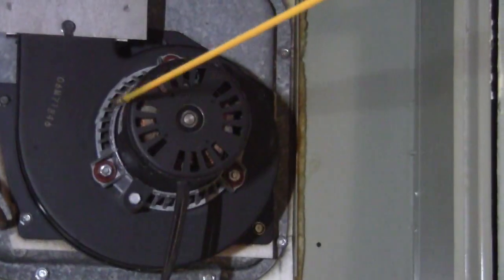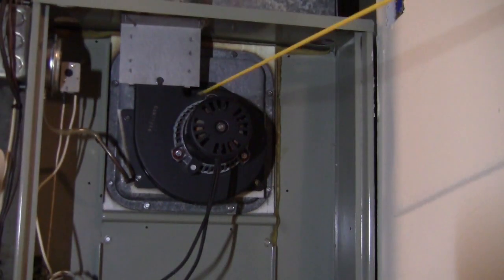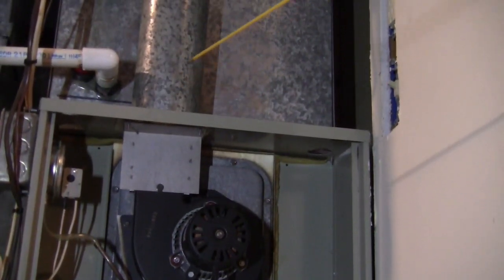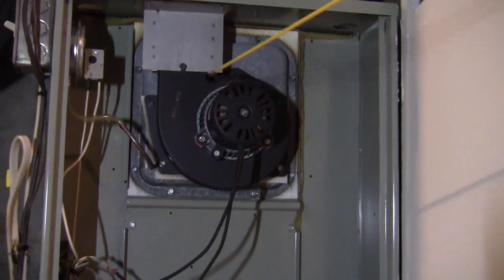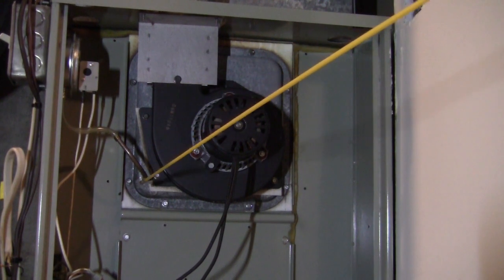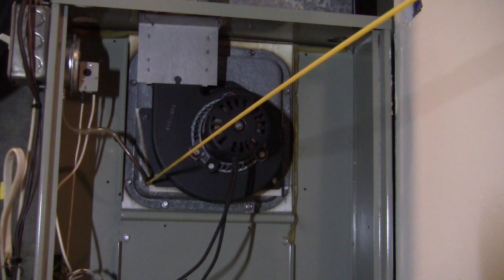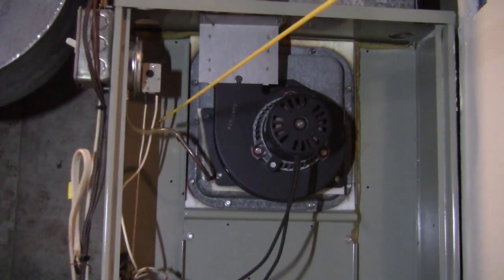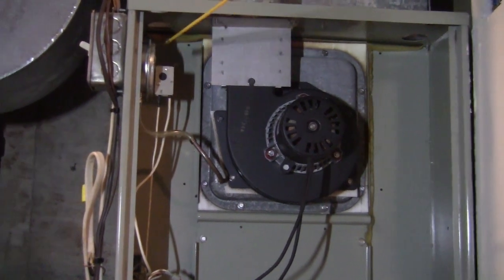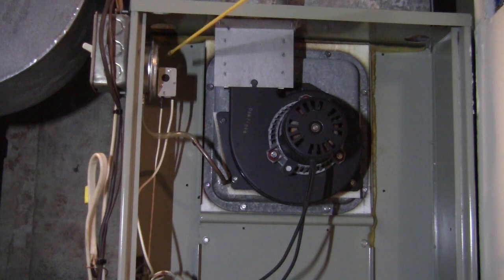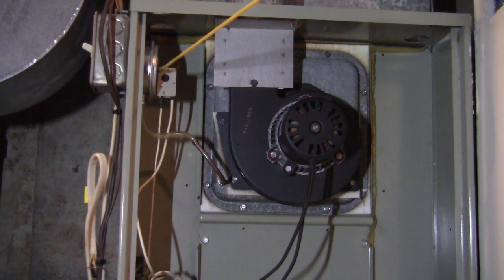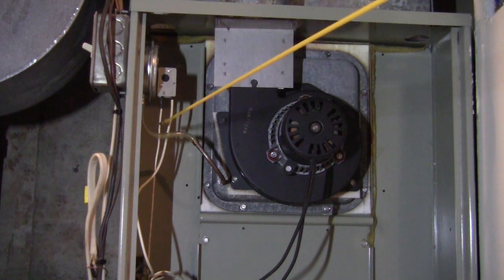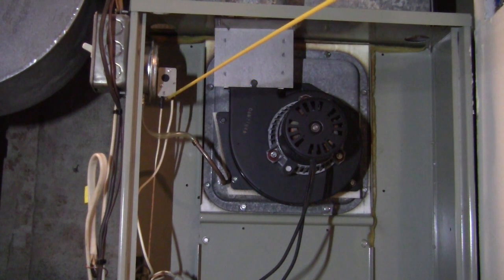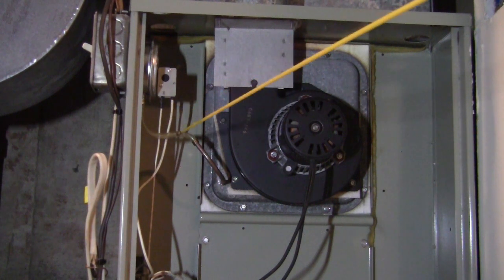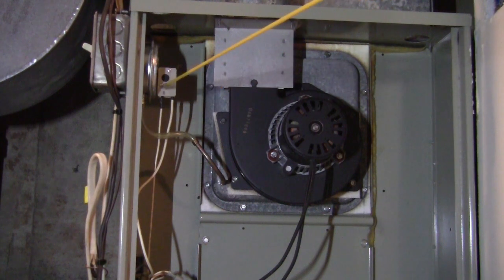Once this fan runs, it sucks up the air from here and blows it up the chimney. So once it sucks up the air, the pressure underneath this chamber will be lower than outside. When it is lower than outside, there is a vacuum through this pipe to this valve. When this vacuum triggers this valve, inside the valve there is a default open switch. Default open means if you don't do anything, these two wires are open. They don't connect to each other.